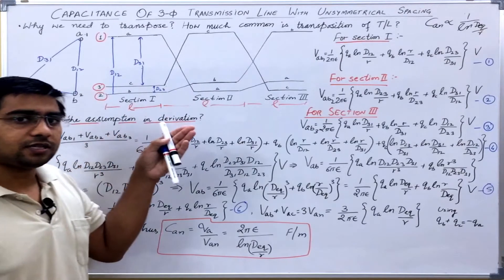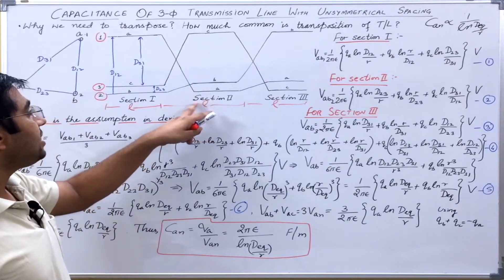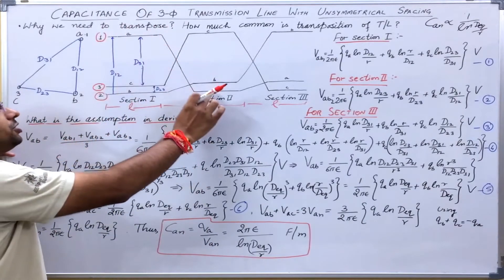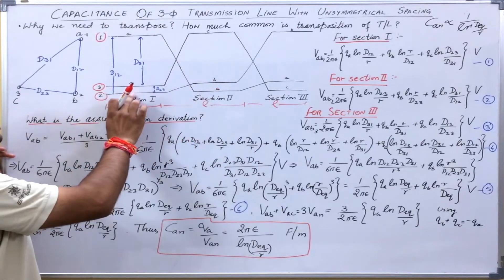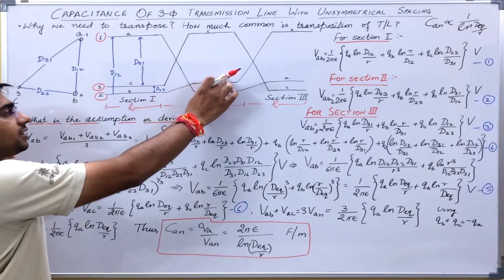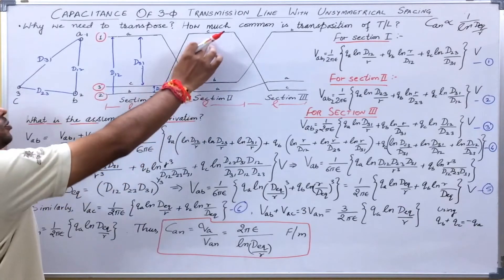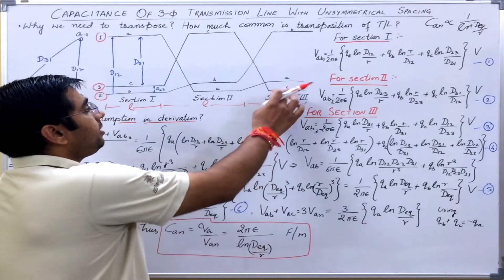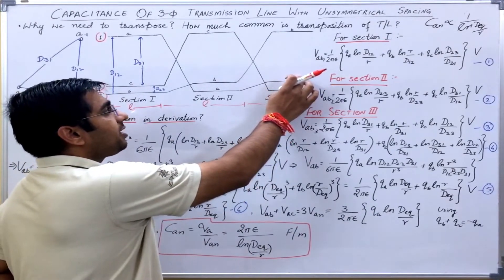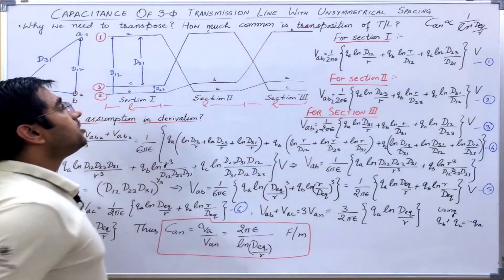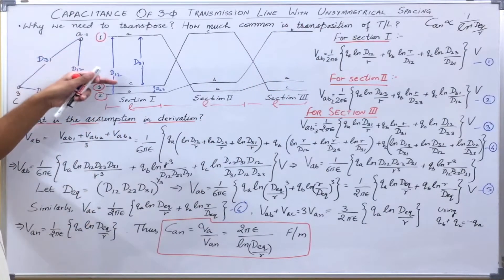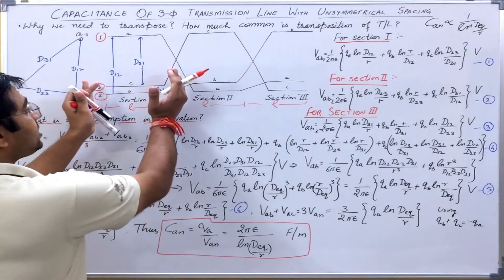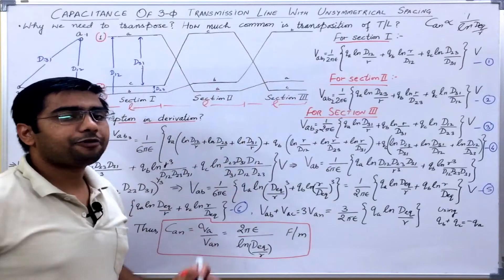After transposition, in section 2: A, which was occupying position 1, will come to position 2; B, which was occupying position 2, will come to position 3; and C will go to position 1. Similarly, in section 3: C will occupy position 2, A will occupy position 3, and B will occupy position 1. So we see that every phase has occupied every possible position, and the length for which that position is occupied is the same for every section. In this way, we try to neutralize any asymmetry that occurs due to unequal spacings.